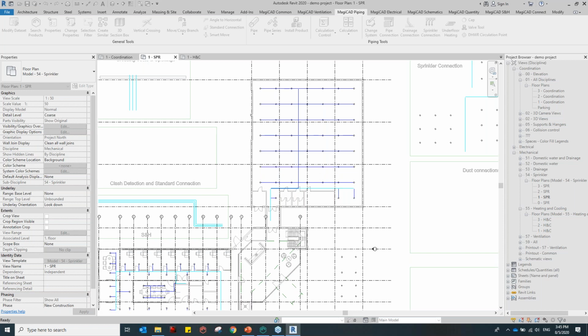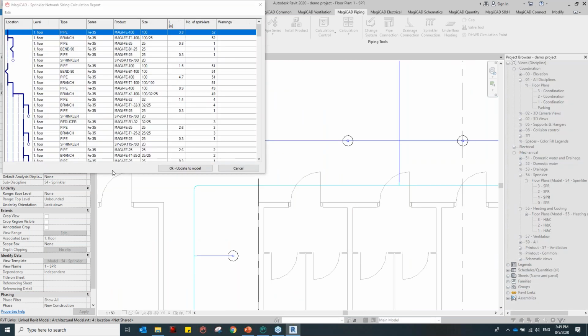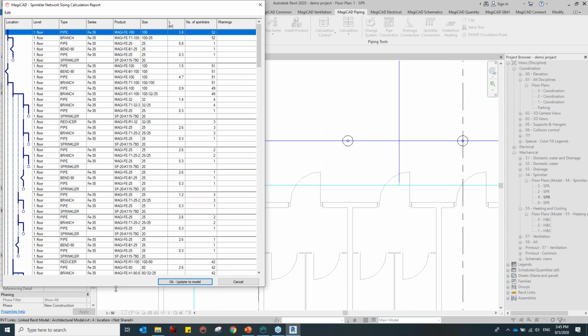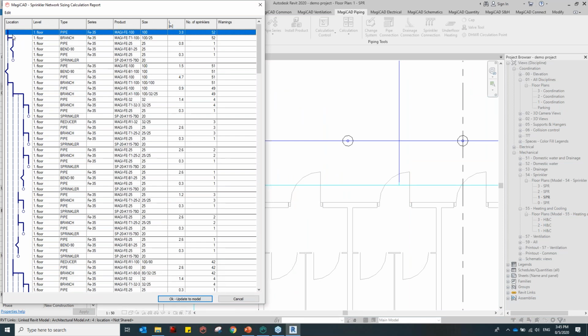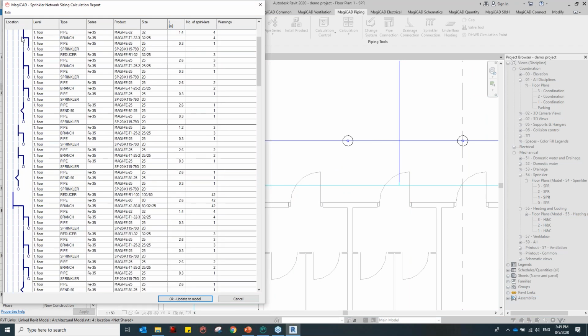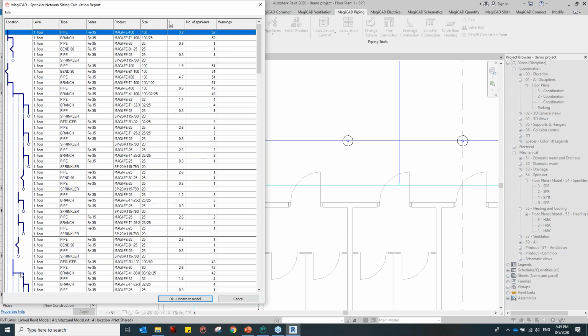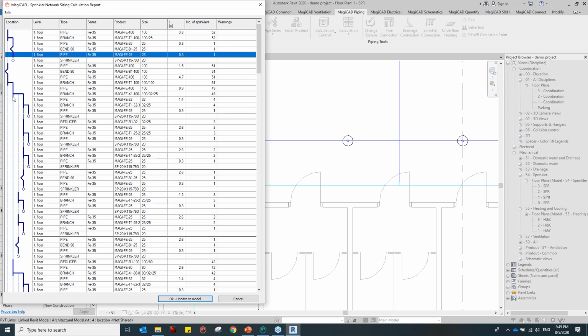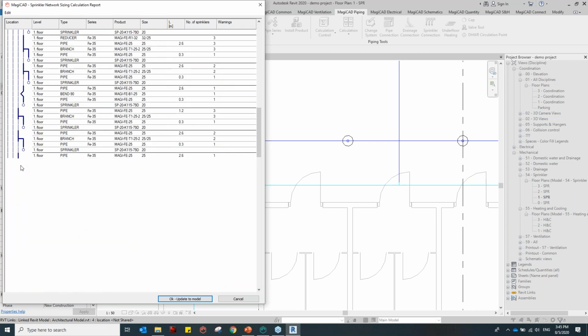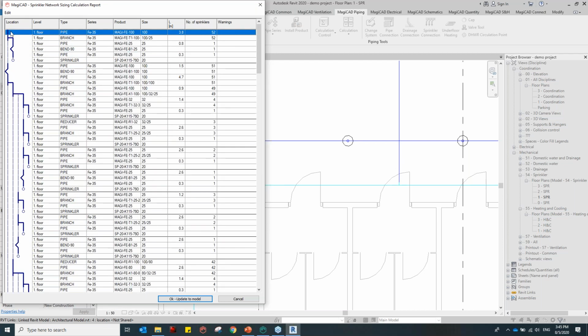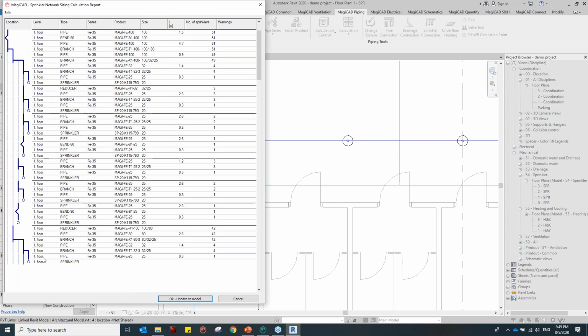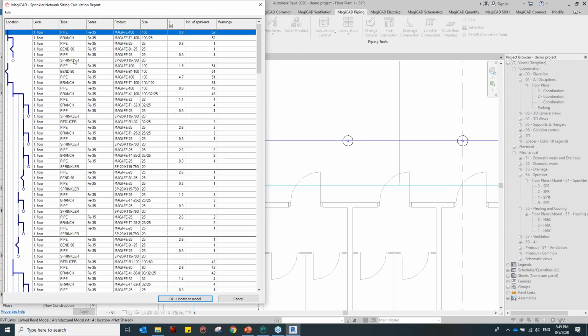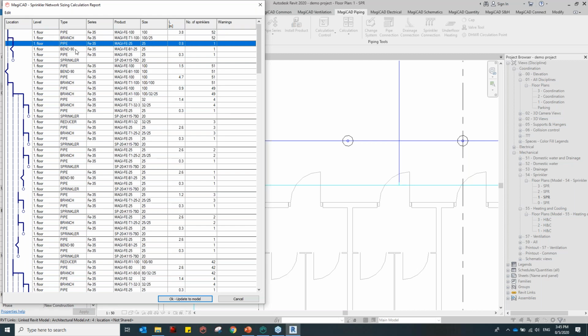If I select any pipe in the network, we can see a simple schematic skeleton diagram automatically generated in the report. This is a sprinkler sizing report generated by MagiCAD, showing the network diagram drawn roughly, which floor it belongs to, and the pipe type of the item, whether it's a branch, a pipe, or a bend.